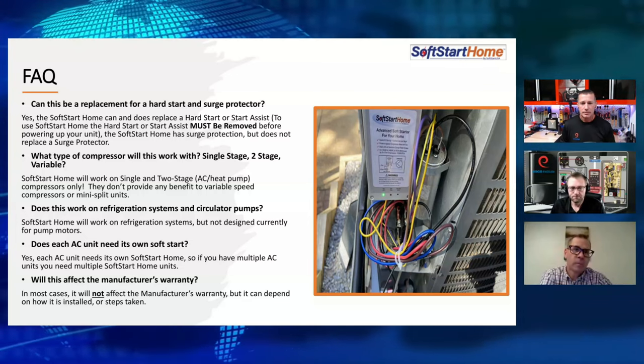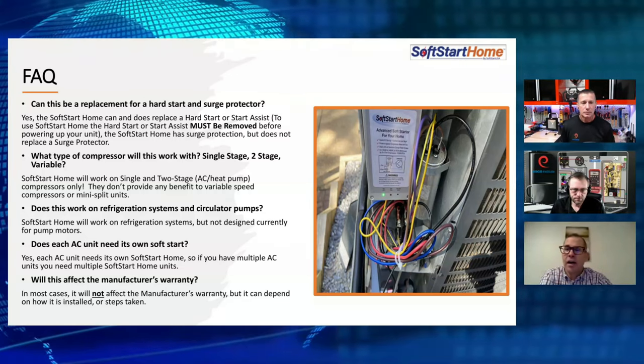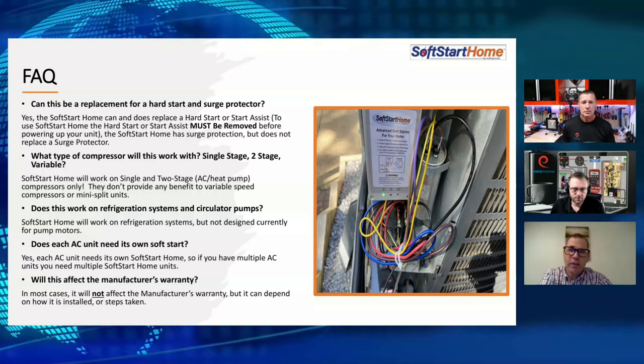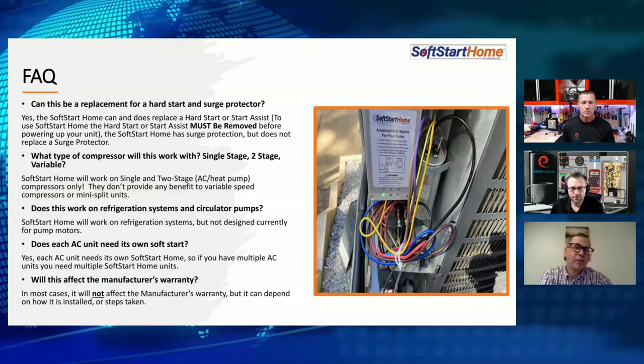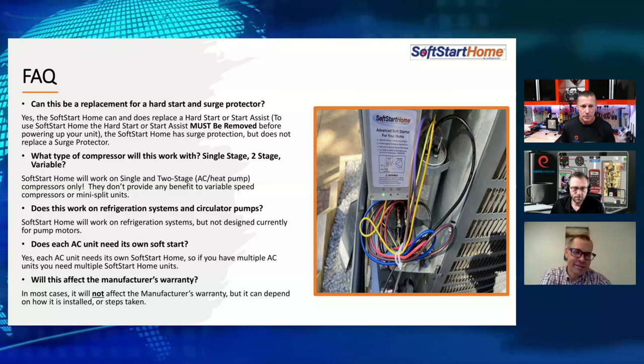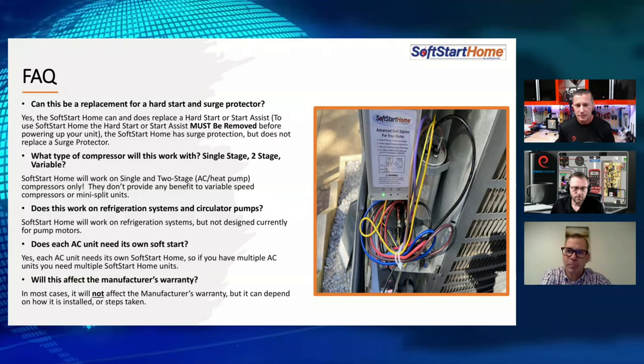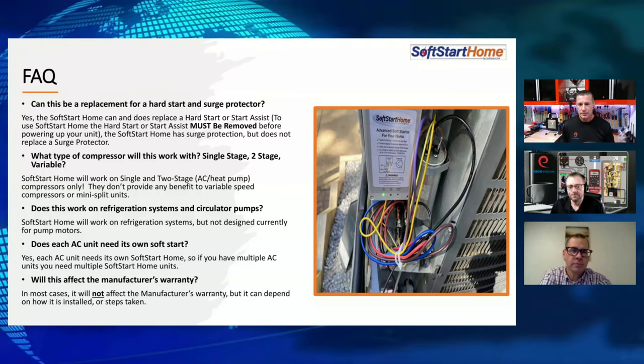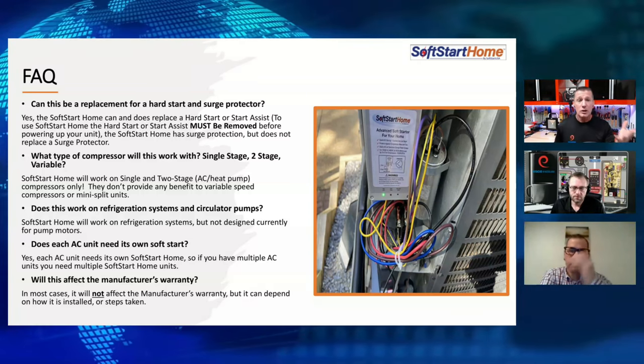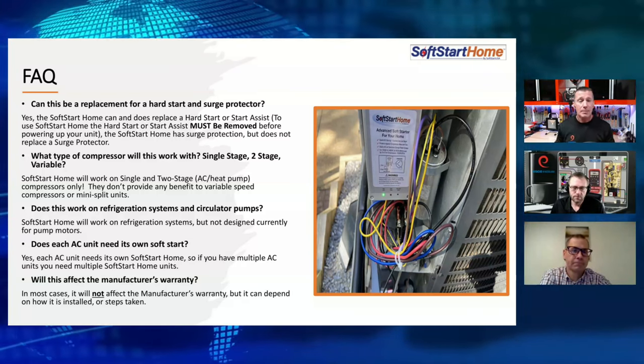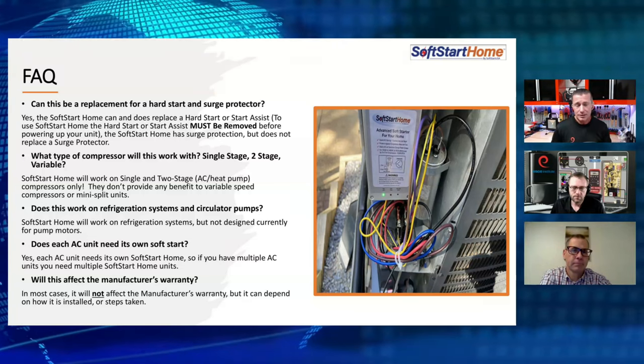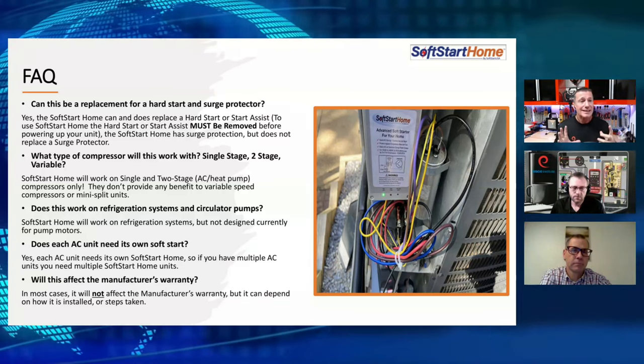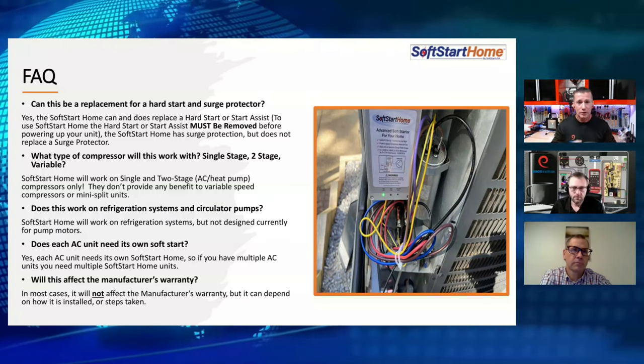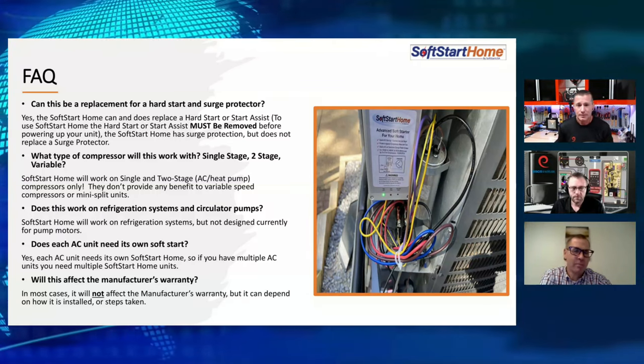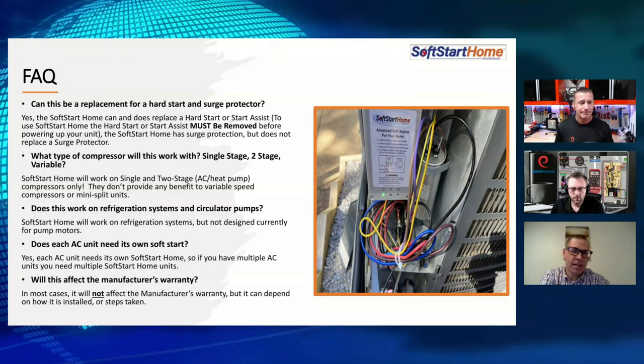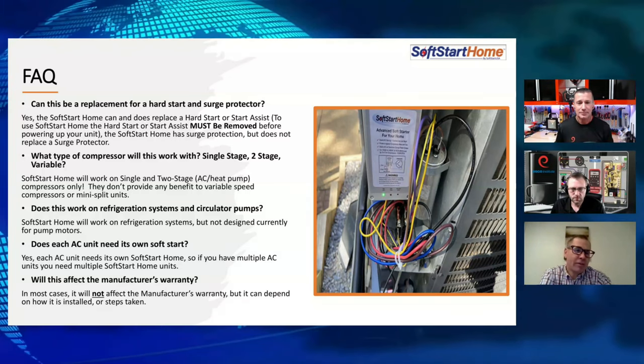As far as the hard start goes, yes, we can be a replacement, but you must remove the hard start to install the soft start—you can't have an additional start assembly on there. We've talked about compressors a little: we're talking about PSC, permanent split capacitor driven compressors. If it has a run capacitor, we're good to go. Mini splits and inverter technology are fantastic, but they already have that built in.